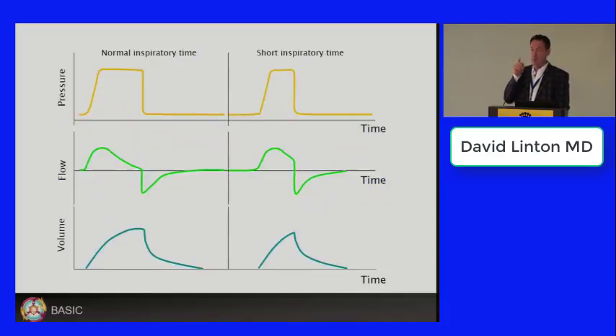But bear in mind that when you're watching this, where are these measurements being taken from in that particular ventilator? You have to know: are they being measured at the end by a flow sensor? Are they being measured in the trachea? Are they being measured as it comes out of the machine? Or are they being measured inside the machine where all the valves are? And it makes a big difference.